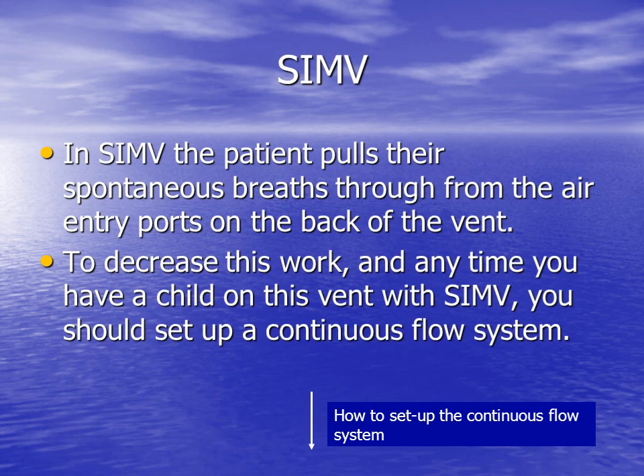SIMV is infrequently used on this vent, but if you are asked to set it up in SIMV mode, there's a few things to keep in mind. Again, the apnea alarm is only functional in the SIMV mode. The I to E window will be blank in SIMV. Patient effort breaths that fail to surpass the lower pressure limit alarm will activate a short, undelayed audible alarm, and that's in addition to starting the 15-second countdown to the continuous audible alarm.